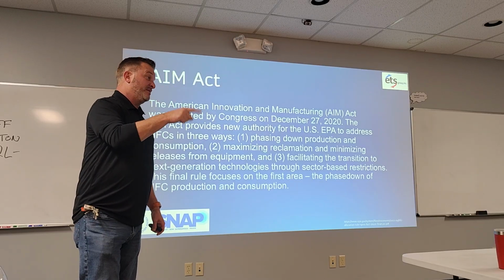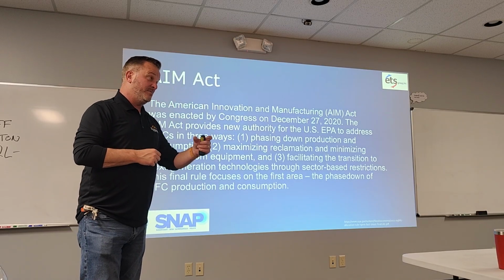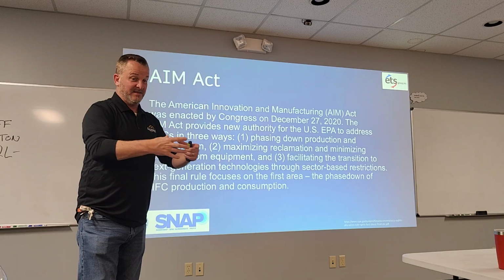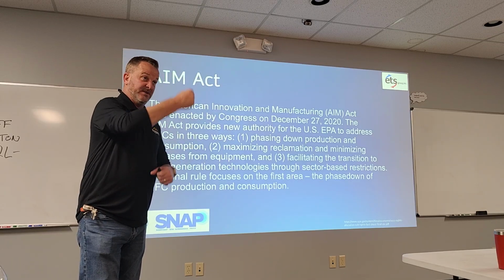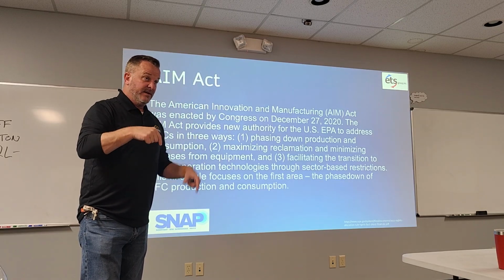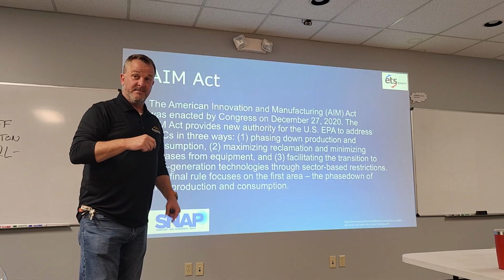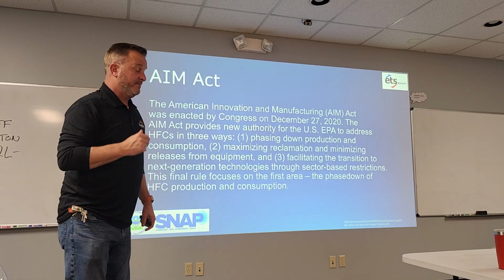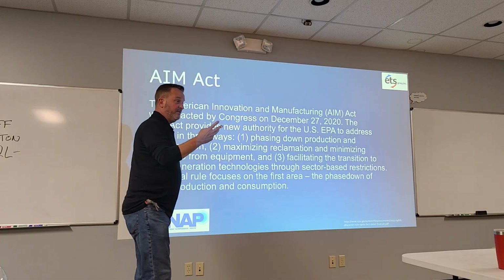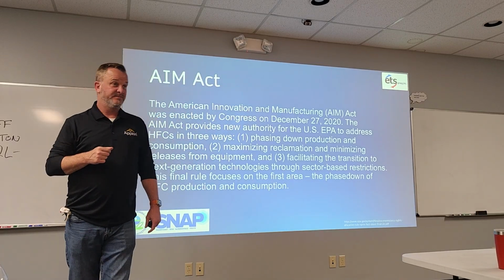And if you don't believe me on the blue coil cleaner, all you've got to do is take a water bottle, put some blue coil cleaner in there, stick something underneath it, take some aluminum foil, drop it down in there, it's going to foam up and over. Leave it in there for a minute, pull that aluminum foil out, it's gone. It's tattered and gone. They say after an average use of three coil cleanings with a foaming coil cleaner, you've eaten 7 to 12% of the mass of that coil.